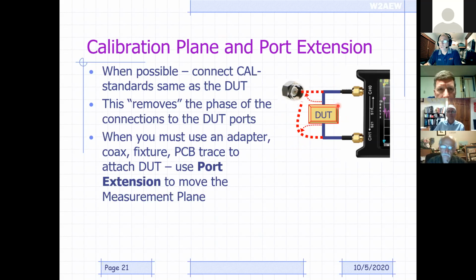Now, sometimes you have a different connector style. My calibration standards are one connector type, but if I'm connecting up to an antenna or something, that's a different connector type. So what do you do? You can use an adapter, use coax, use a fixture, or do something else to connect your standard to your device. So what do you do if you want to remove that from the measurement? One thing you can do is something called port extensions.